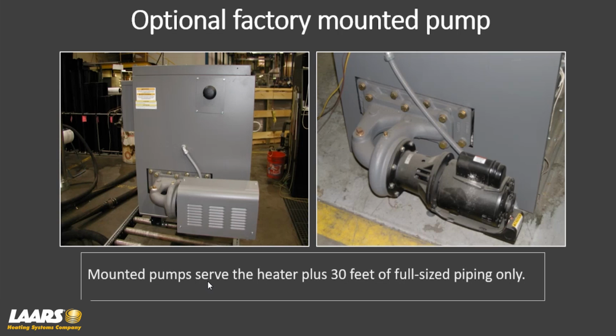Now, pump mounted, we serve the heat exchanger plus 30 feet of full-size piping is how it's listed. That means we're going to cover the head loss in the heat exchanger plus 15 feet out to the system and 15 feet back. So if you have a hydronic system, hypothetically, primary, secondary, again, 15 feet out to the system loop and 15 feet back. V models for volume water heating, maybe you have a storage tank, that's going to be sized for 15 feet out to the tank and 15 feet back to the boiler.